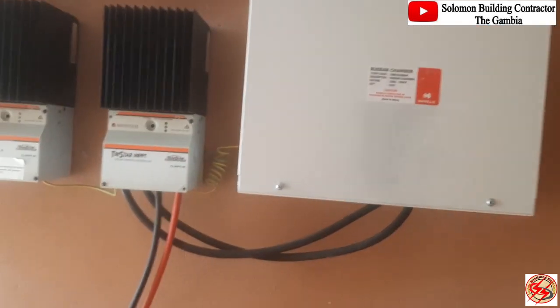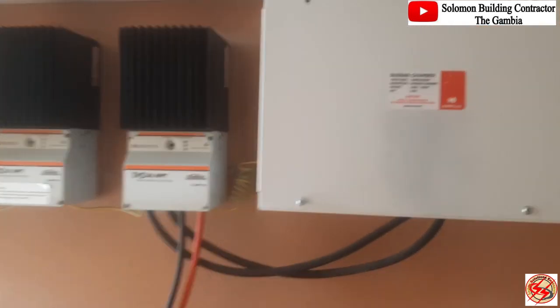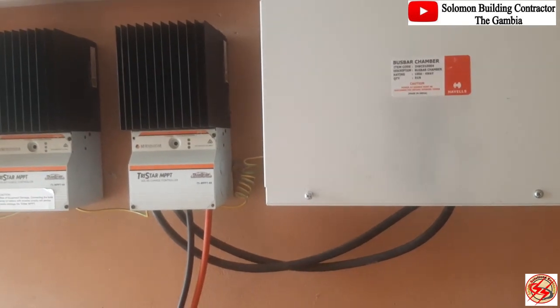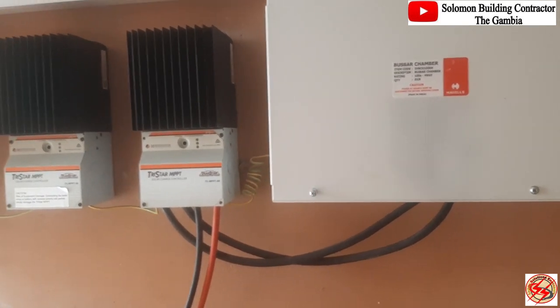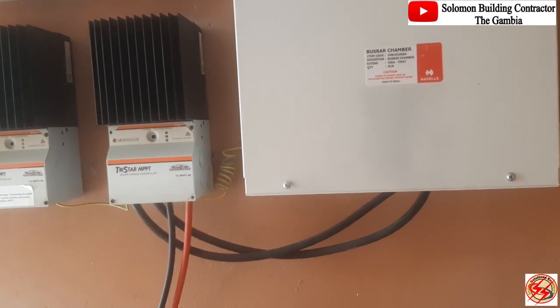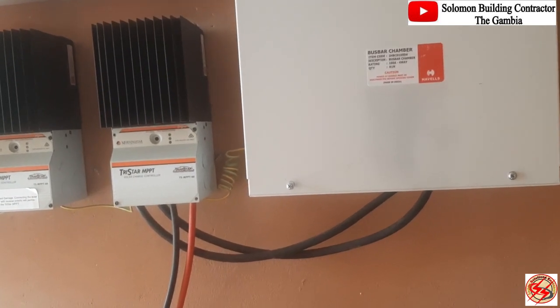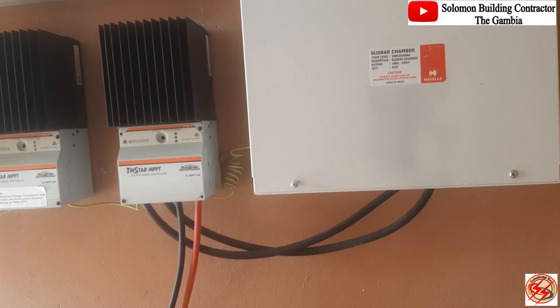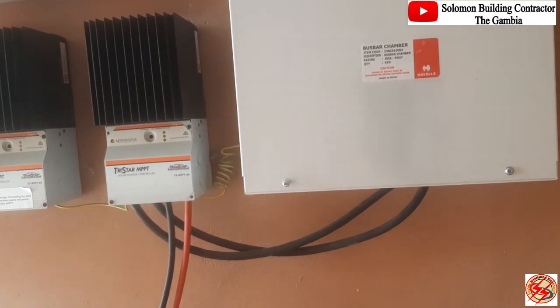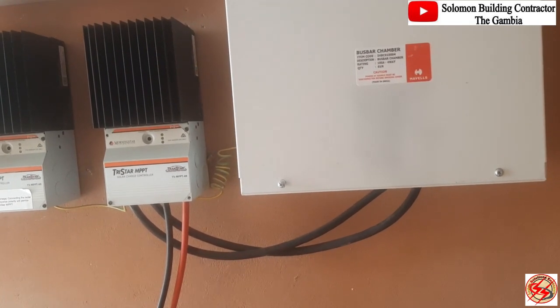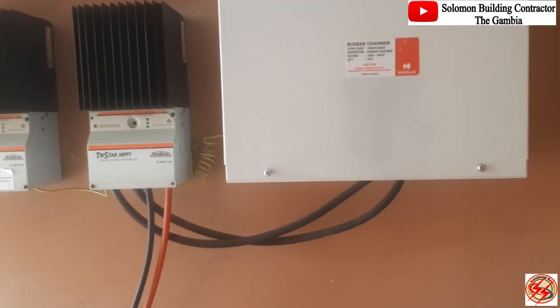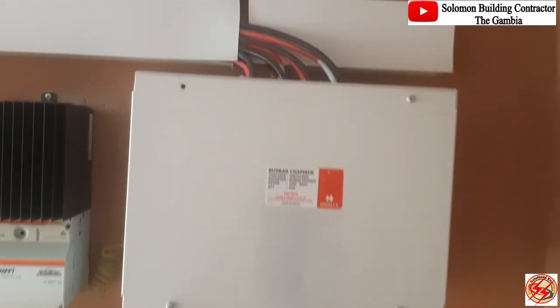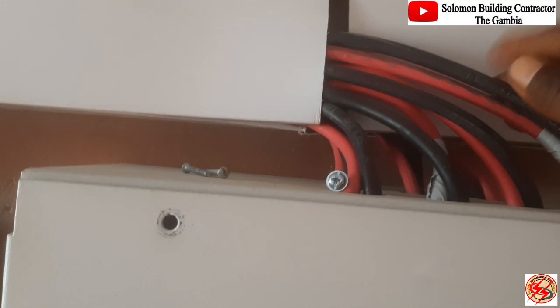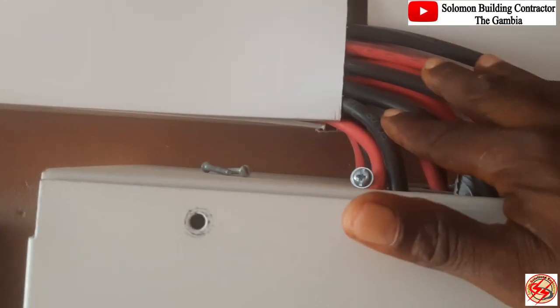So you build circuits: what I call a circuit is you group them in 4. Every 4, you drop down. For each group of 4 you build a circuit, and what helps you build that circuit is this busbar. You can see a lot of wires coming in here from each of the circuits from the panels upstairs. This cable actually comes from the panels.